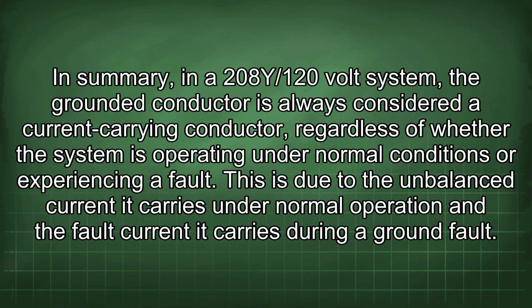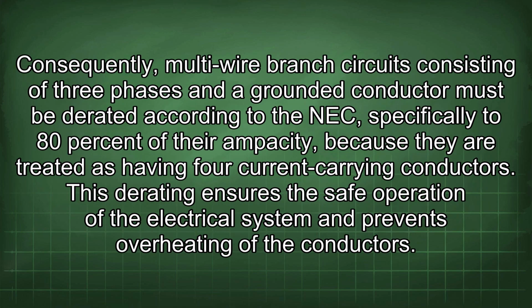In summary, in the 208Y/120 volt system, the grounded conductor is always considered a current-carrying conductor, regardless of whether the system is operating under normal conditions or experiencing a fault. This is due to the unbalanced current it carries under normal operation and the fault current it carries during a ground fault. Consequently, multi-wire branch circuits consisting of 3 phases and a grounded conductor must be derated according to the NEC, specifically to 80% of their ampacity, because they are treated as having 4 current-carrying conductors. This derating ensures the safe operation of the electrical system and prevents overheating of the conductors.